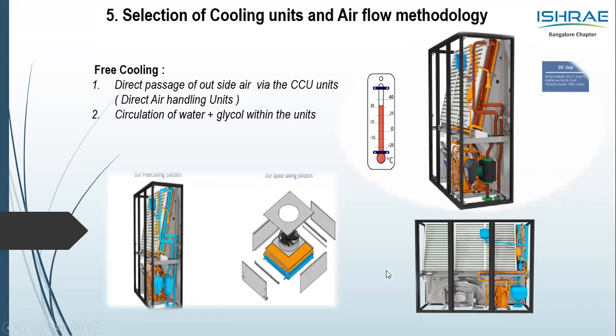In this, the benefit is that as the ambient lowers and is within the bracket, it can be within free cooling or it can be within the mixed mode. So compared to a normal CRAC unit or a CCU unit without the free cooling, you get a good saving in the operational time of the unit throughout the year. Again, it depends upon the location of the unit where it is placed, whether it is Bangalore or Delhi, where you have the advantage of lower ambient in a few of the months.